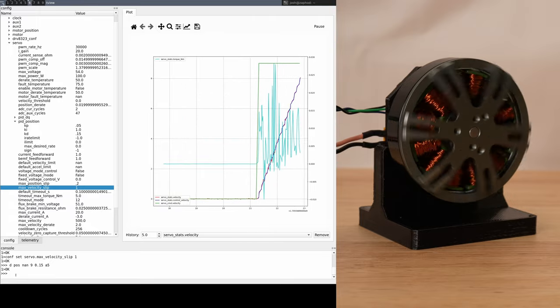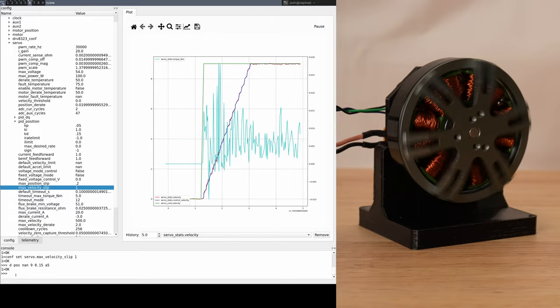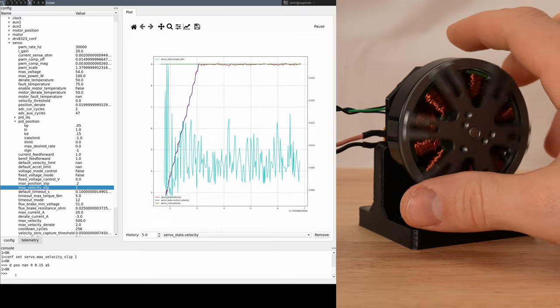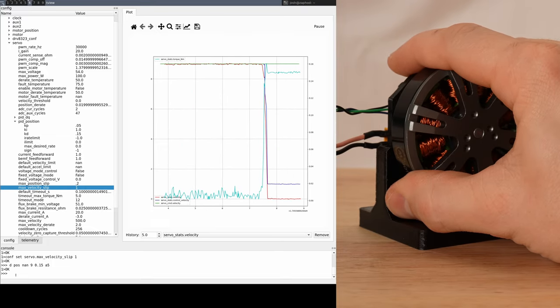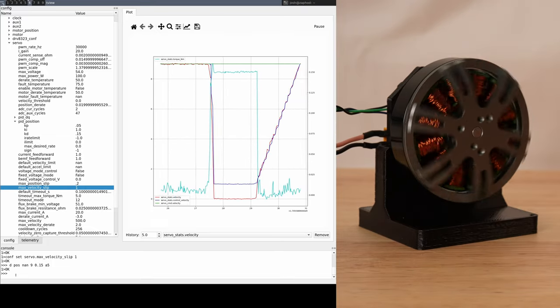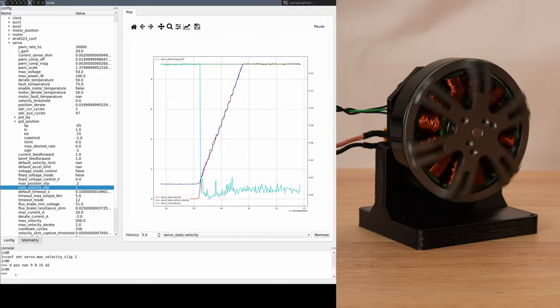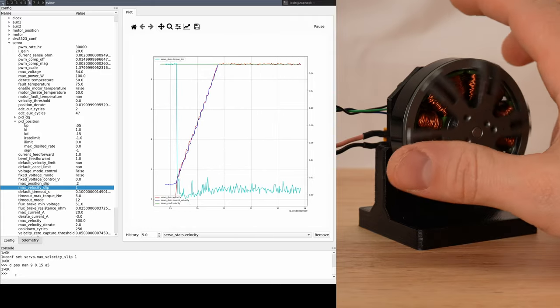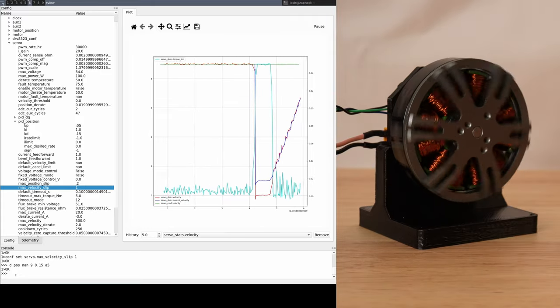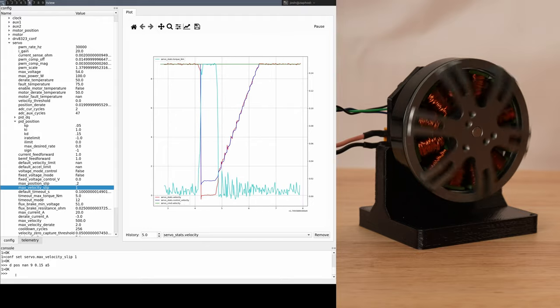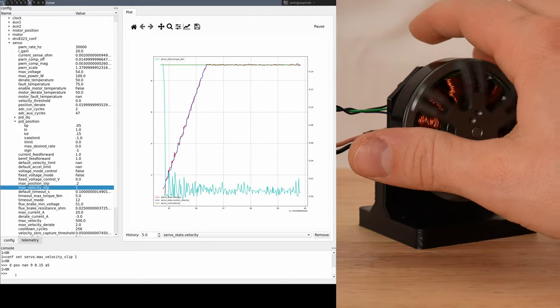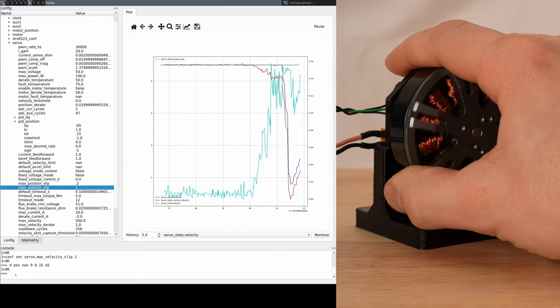I'll send the initial command and watch the motor spin up. Now I'll restrain it with my hand down to 0 speed. Here we can now see that the control velocity has dropped down and is hovering around 1 Hz. When I release my hand, the motor gradually spins back up following our commanded acceleration limit.